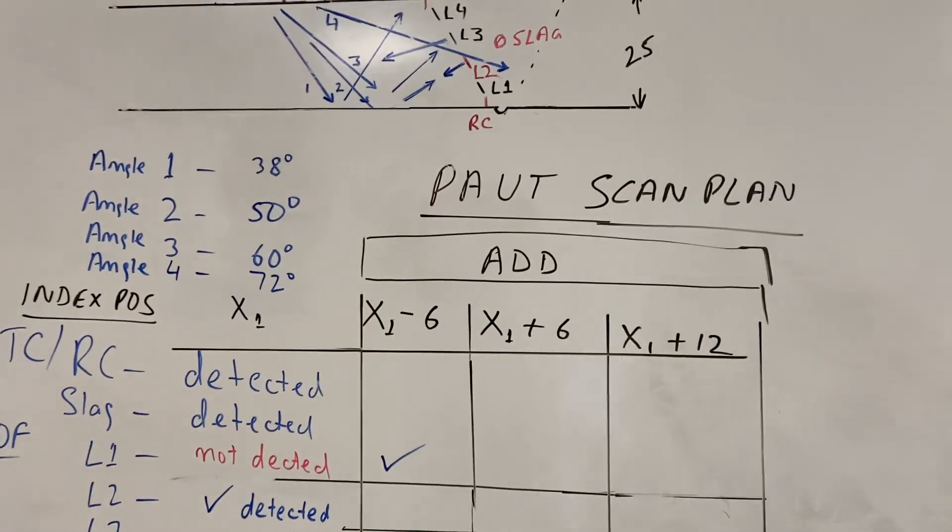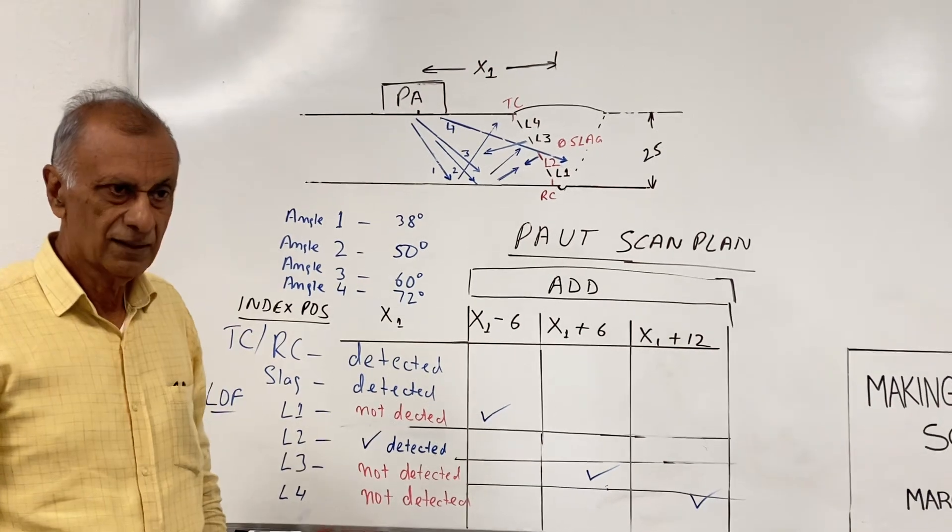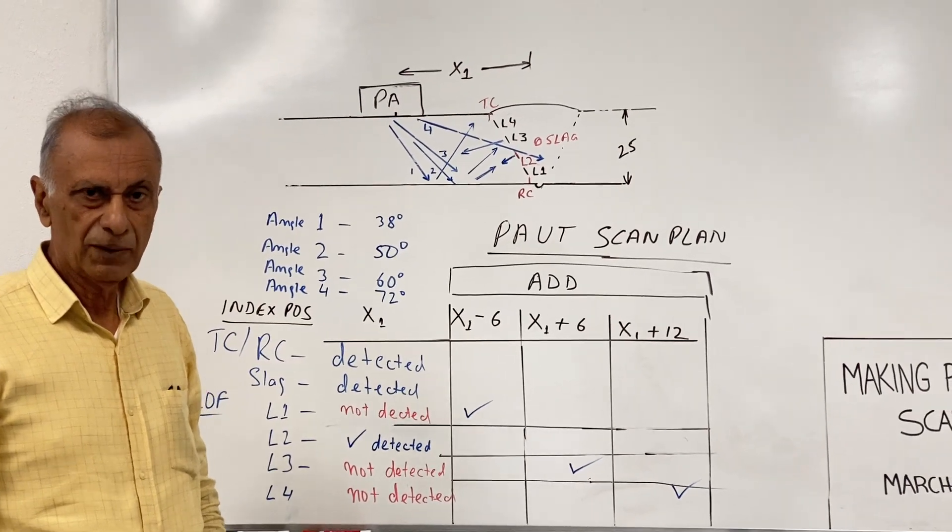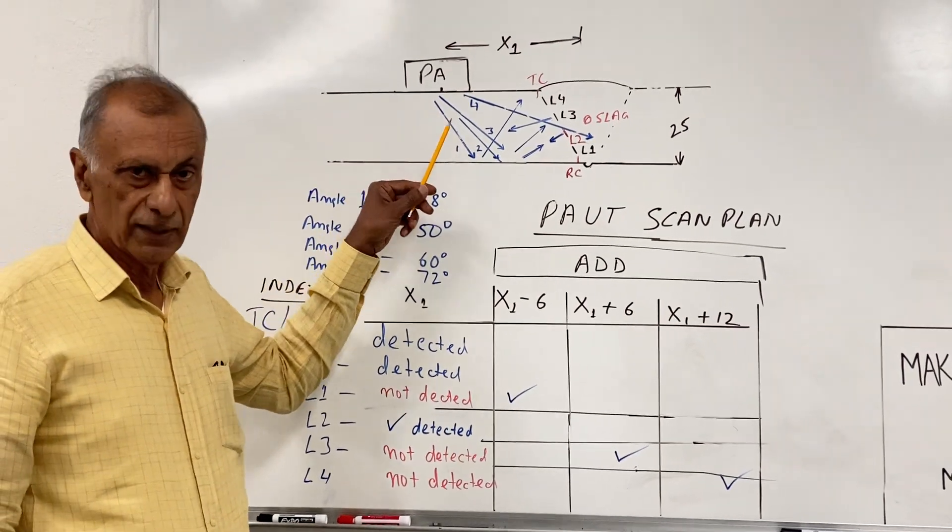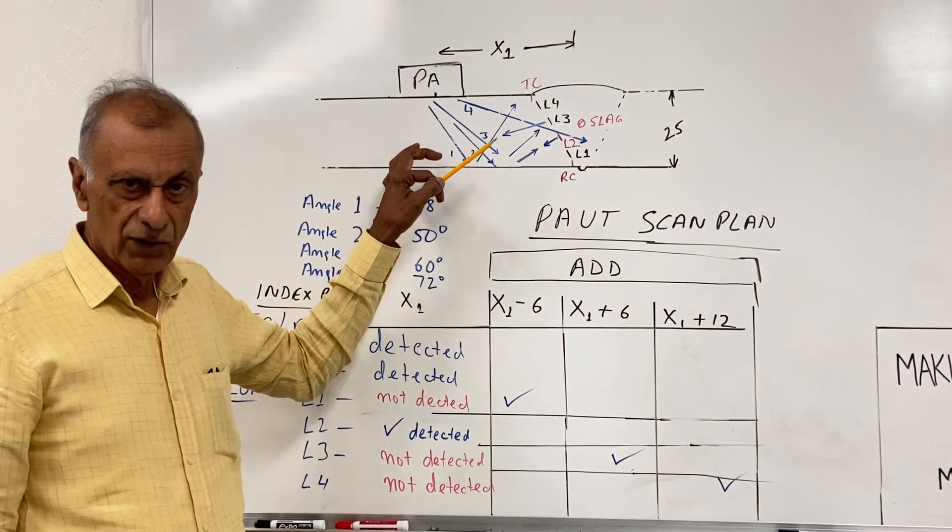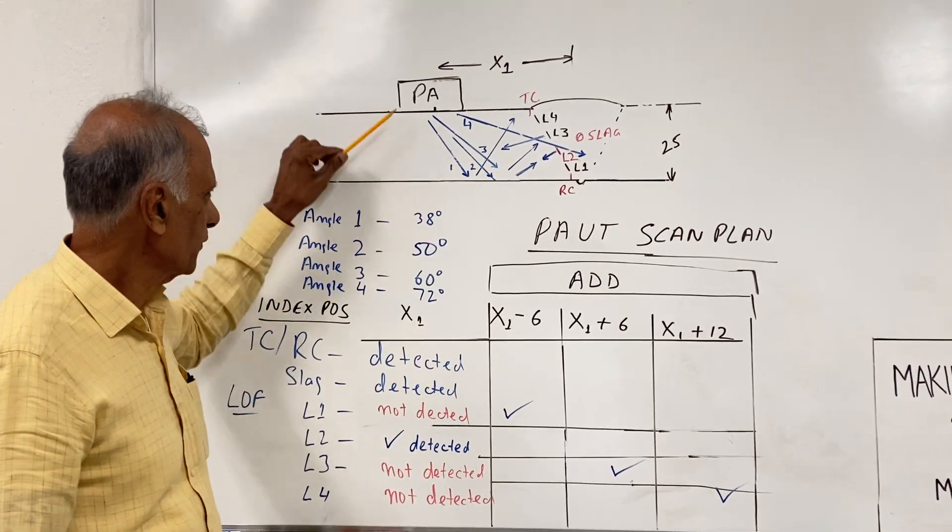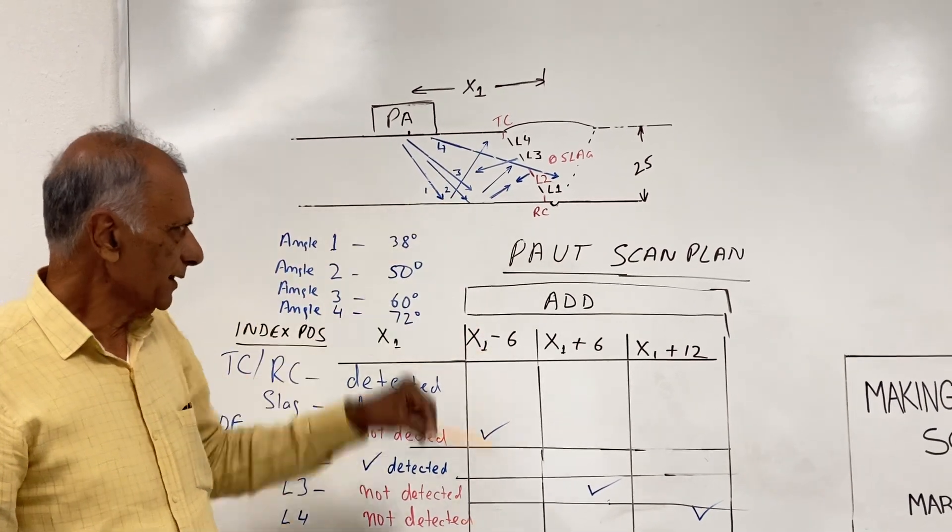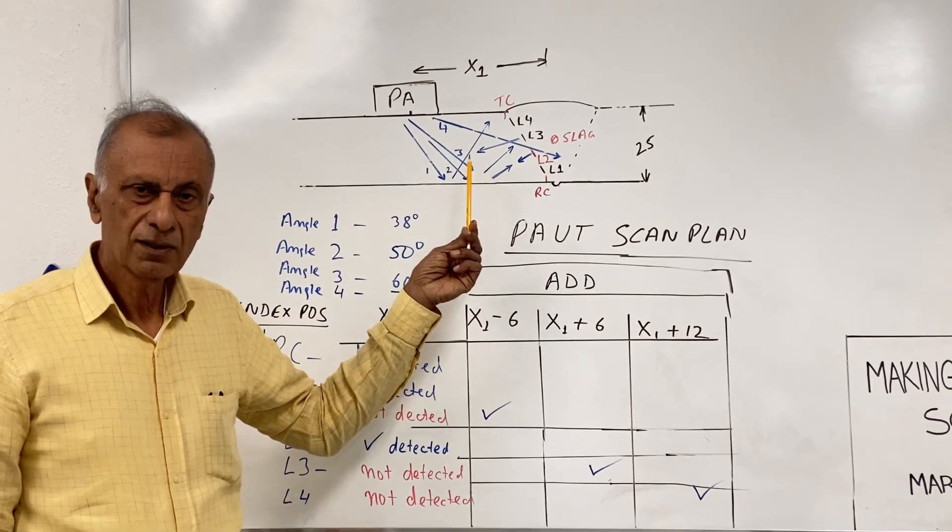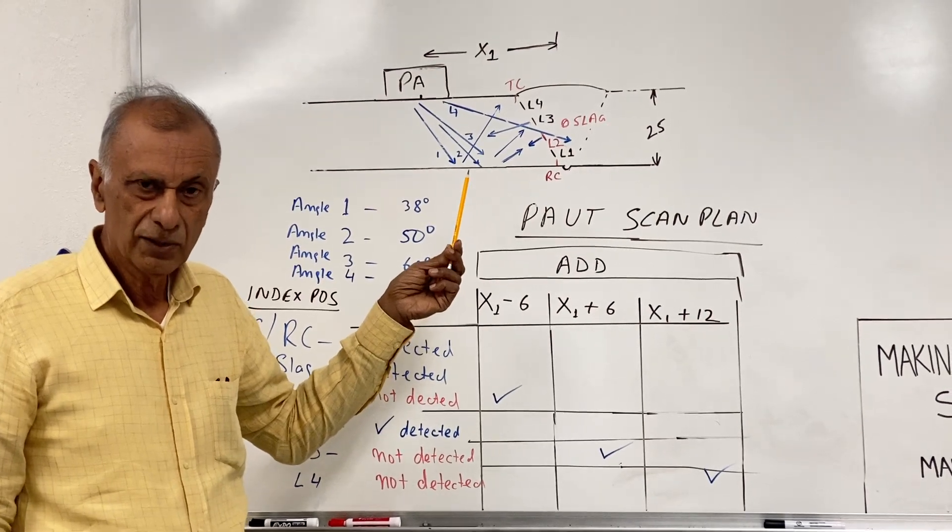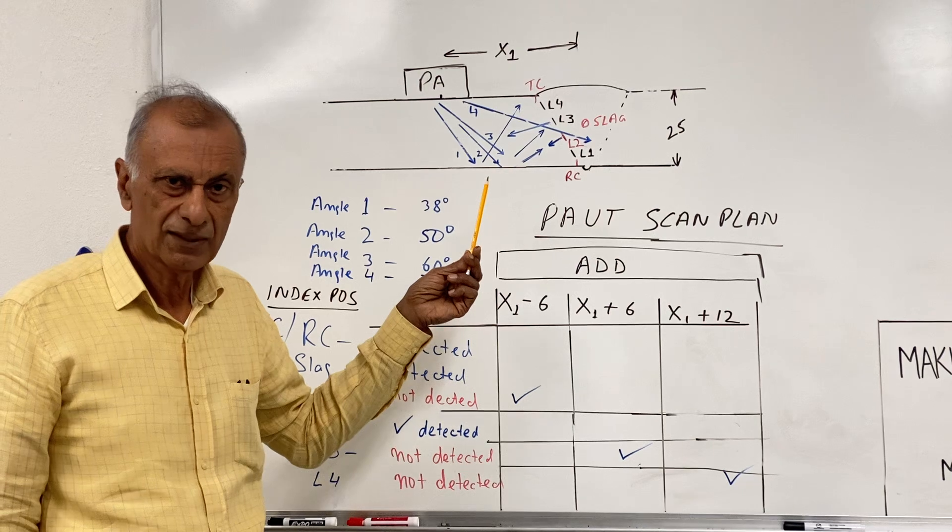Now let's go to the next step, which is the scan plan. This is a very big issue right now as far as the scan plan is concerned. What I've seen is that many people will show a scan plan with a probe sitting here, and they will show that the whole weld is getting illuminated. They will have a scan plan from 40 degrees or 38 degrees to 72 degrees, and they will show these angles, and they will show that the whole weld has been flooded with sound or has been illuminated with sound. So they are saying that they are getting full 100% weld coverage.